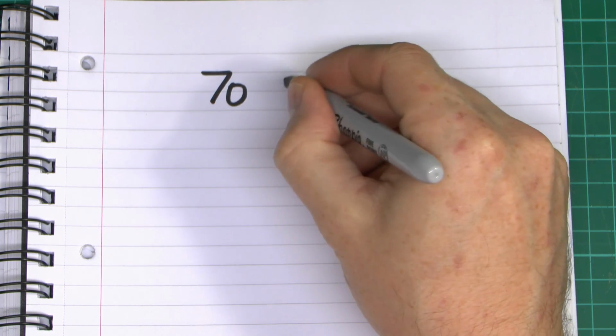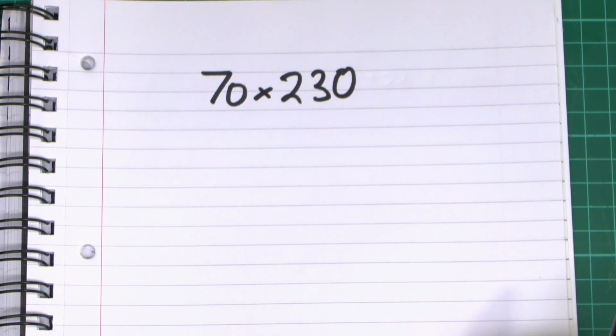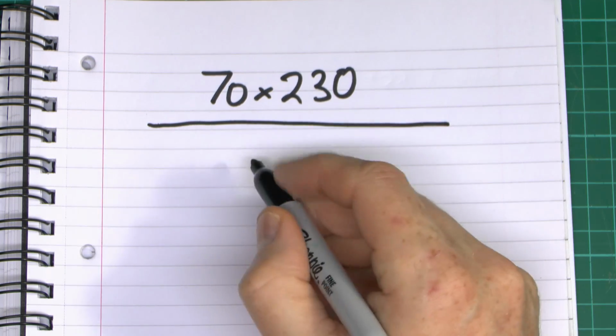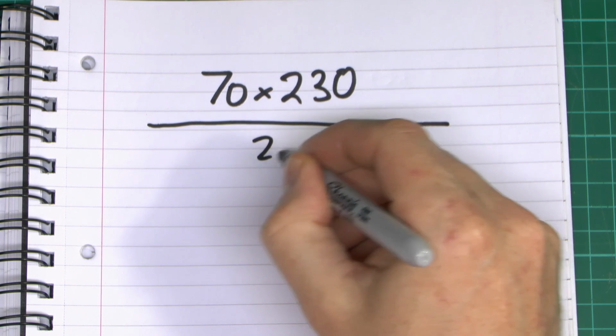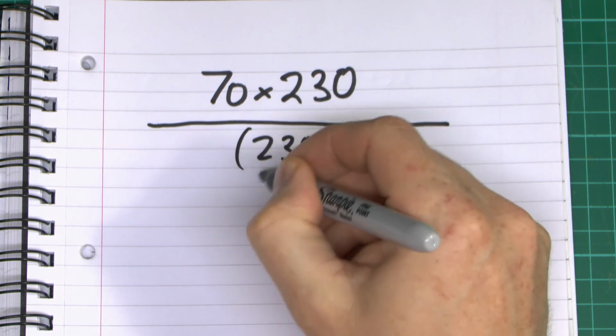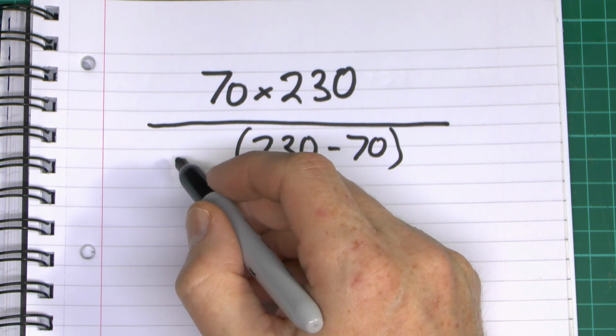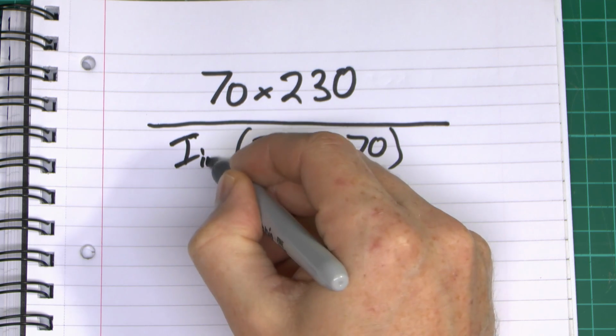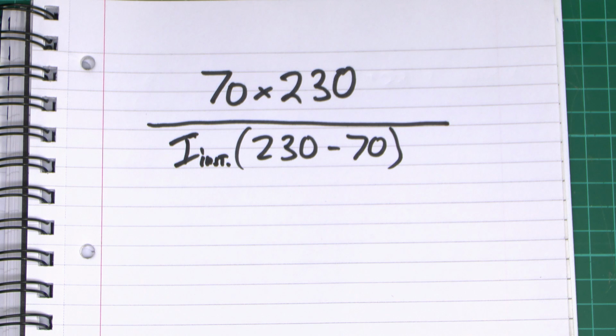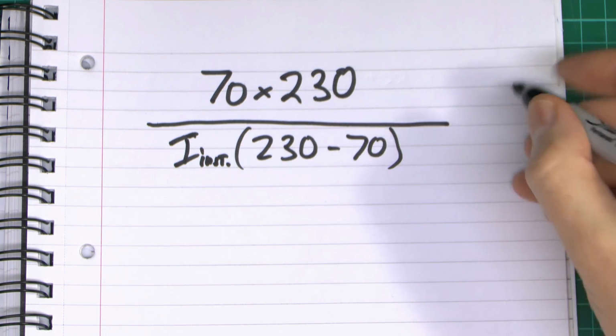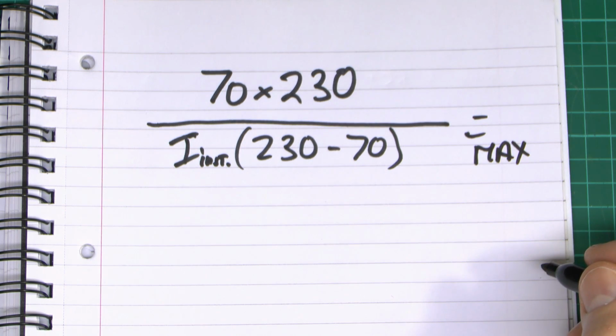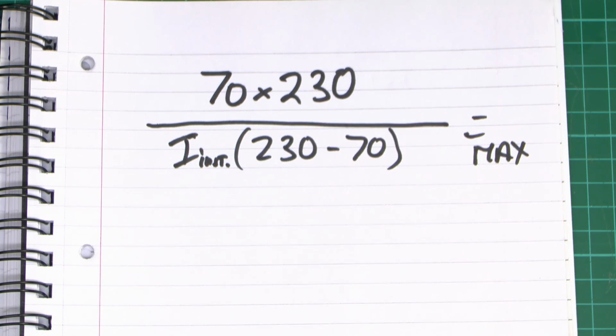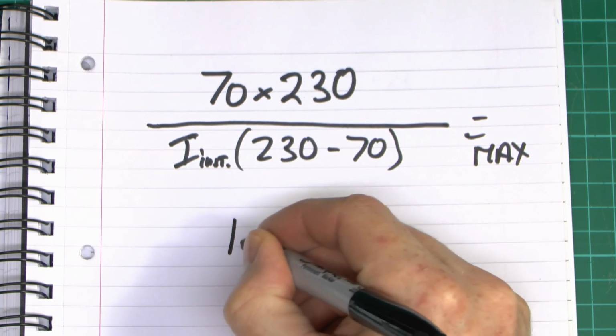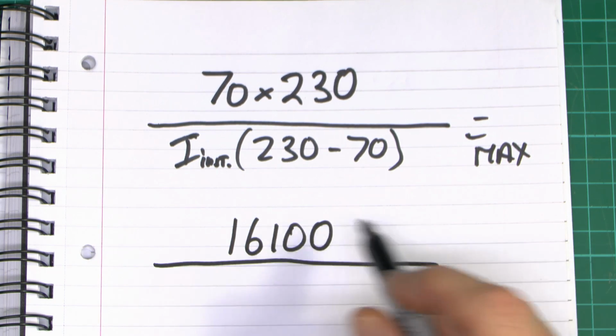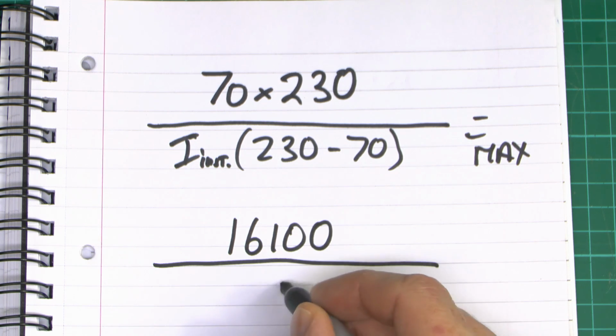and then it's U0, so we use the 230 for that. So those two are multiplied together, and then that's divided by U0 minus 70, so that's basically going to be 230 minus the 70. And then the value here is the actual current of the installation. Now we'll just put that in as I inst for the moment, and that's basically multiplied by that as well. And whatever the result of this is, that's the maximum for the actual resistance of the electrode and the conductor. Now to make that a bit easier, just rewrite this with the actual things calculated there. So the value at the top is 70 times 230, which is 16100. And then at the bottom, the 230 minus 70. Of course, that's going to be 160.